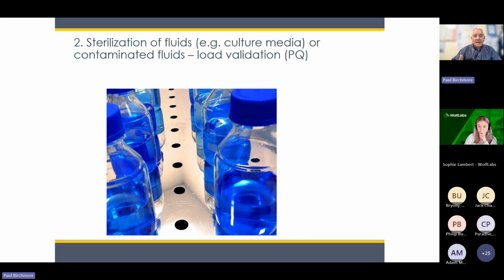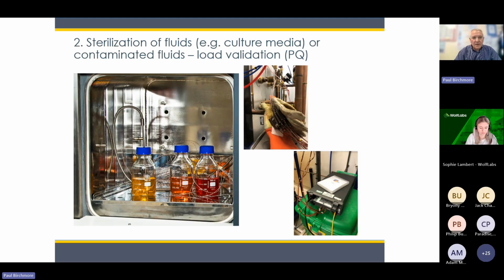But then thinking about that concept of evidence of full effectiveness, coming back a couple of steps, how do you prove on a media load that you've had effective sterilization? Well, this is where we get into load validation or performance qualification, PQ. It's normal in a setup, even though we've talked about these nominal 121 for 15 minutes.